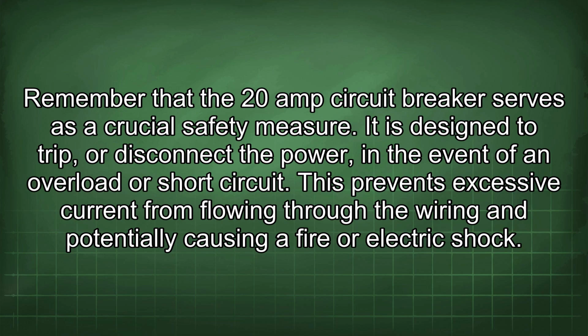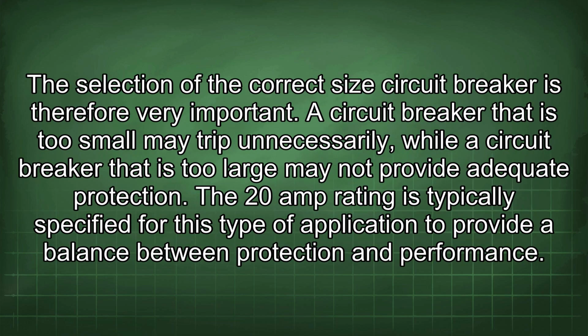Remember that the 20 amp circuit breaker serves as a crucial safety measure. It is designed to trip or disconnect the power in the event of an overload or short circuit. This prevents excessive current from flowing through the wiring and potentially causing a fire or electric shock. The selection of the correct size circuit breaker is therefore very important. A circuit breaker that is too small may trip unnecessarily, while a circuit breaker that is too large may not provide adequate protection. A 20 amp rating is typically specified for this type of application to provide a balance between protection and performance.